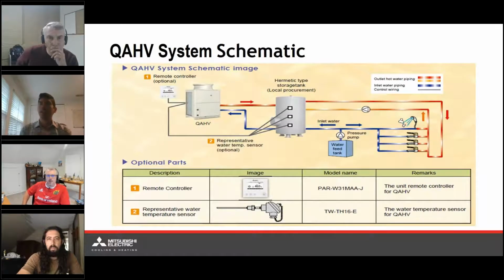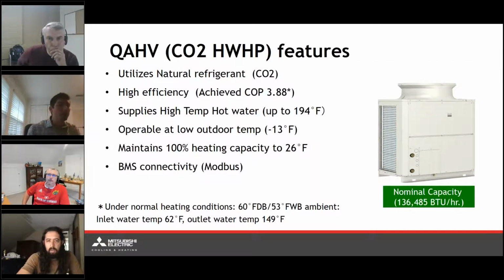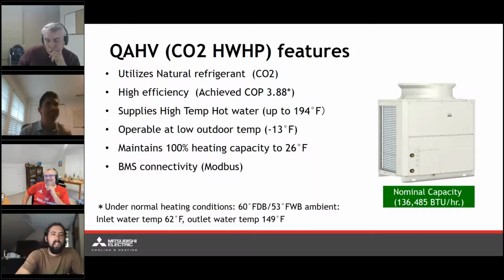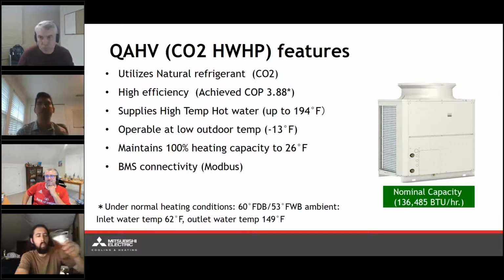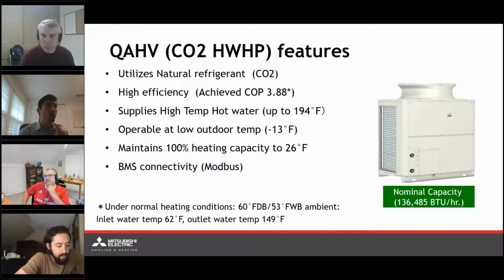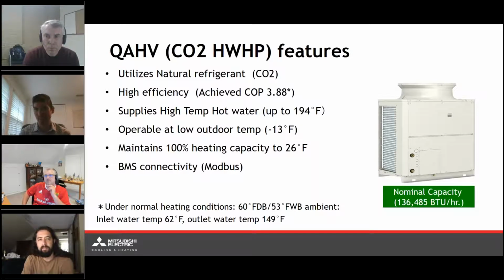All right. So is that where you have a backup heating on it? I'm sorry, can you repeat that one more time? Yeah, no problem. So you're saying here about the capacity being reduced. Would you have backup heating on these if the capacity is being reduced, or how would you take that into consideration? So I don't want to answer that until I have a little bit more engineering data. The current engineering data book I have is dated 2015. And typically if I see that date on a data book, I'm thinking that, all right, a lot more testing has been done. I need more up-to-date info. But with that said, in terms of sizing for any backup heating, what you would need, it would all need to be comprehensively developed, the system as a whole. So again, this is not an on-demand water heating type of situation.